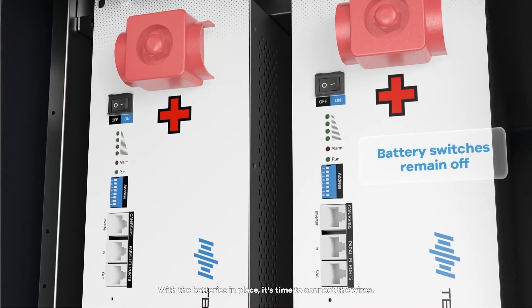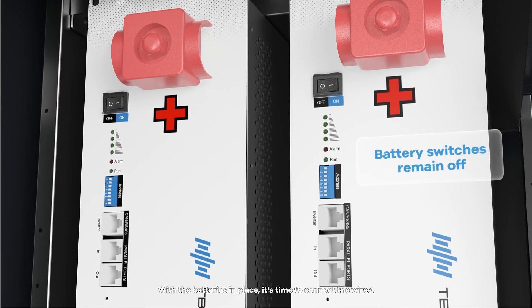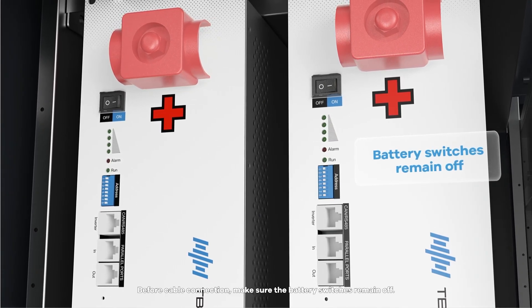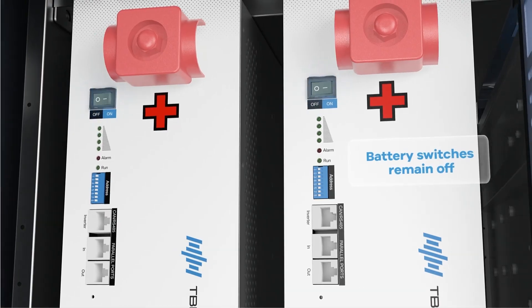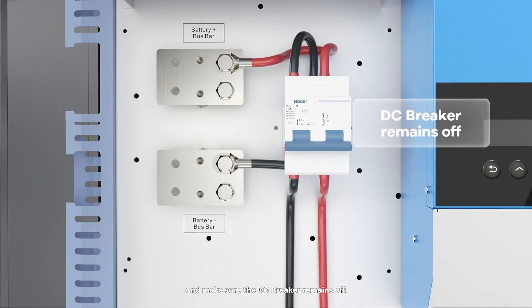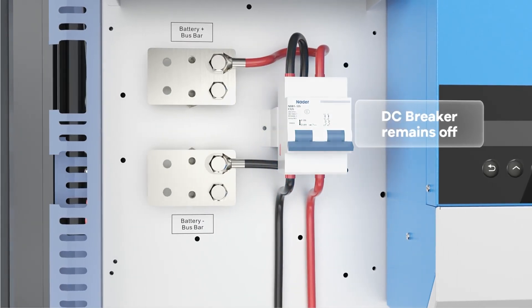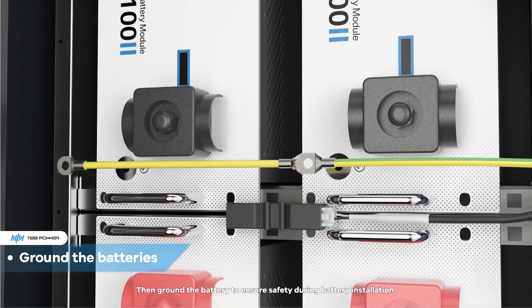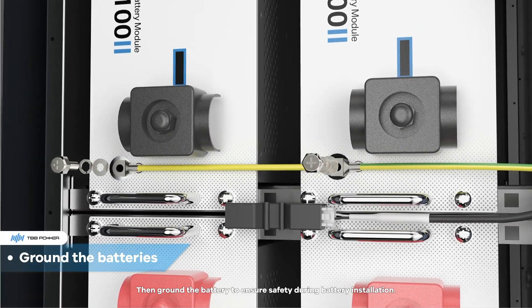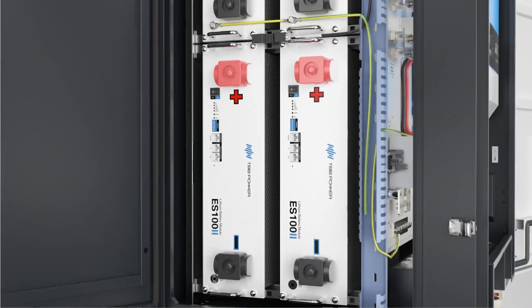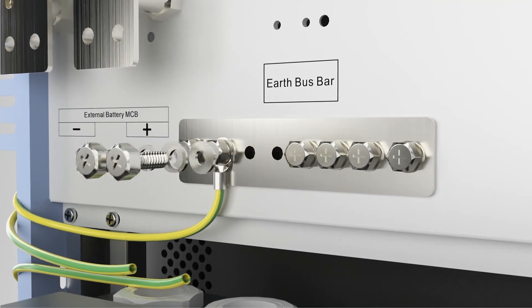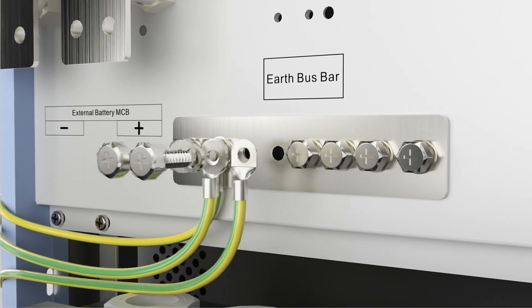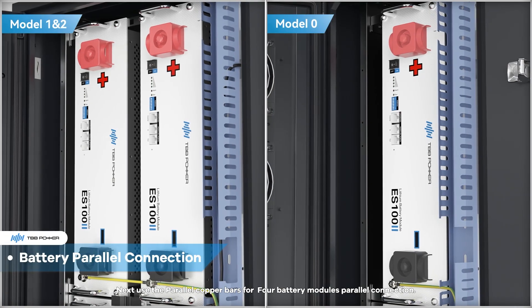With the batteries in place, it's time to connect the wires. Before cable connection, make sure the battery switches remain off and make sure the DC breaker remains off. Then ground the battery to ensure safety during battery installation.